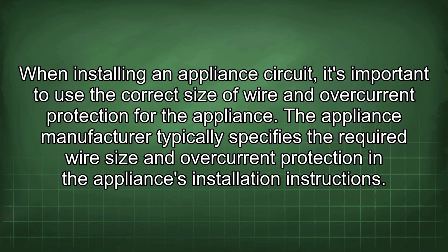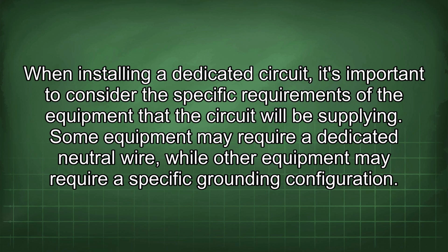When installing an appliance circuit, it's important to use the correct size of wire and overcurrent protection for the appliance. The appliance manufacturer typically specifies the required wire size and overcurrent protection in the appliance's installation instructions. When installing a dedicated circuit, it's important to consider the specific requirements of the equipment that the circuit will be supplying. Some equipment may require a dedicated neutral wire, while other equipment may require a specific grounding configuration.